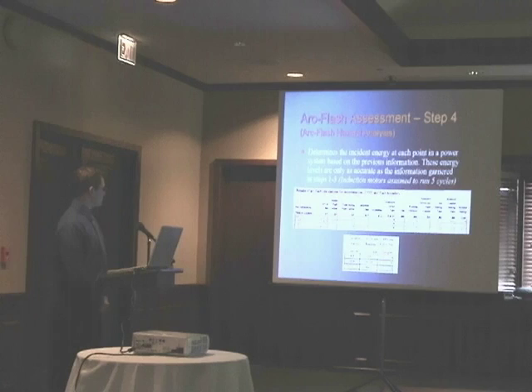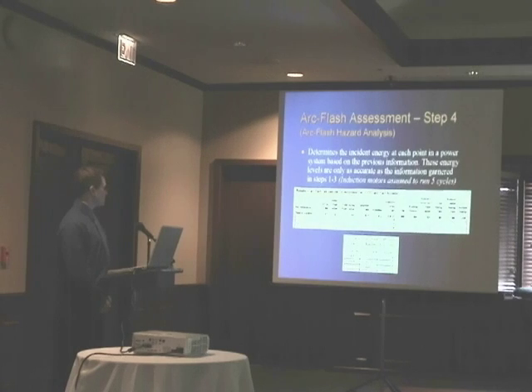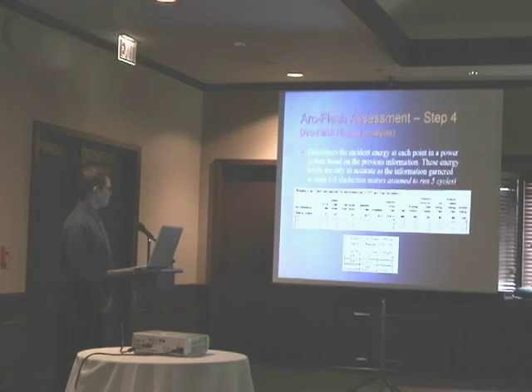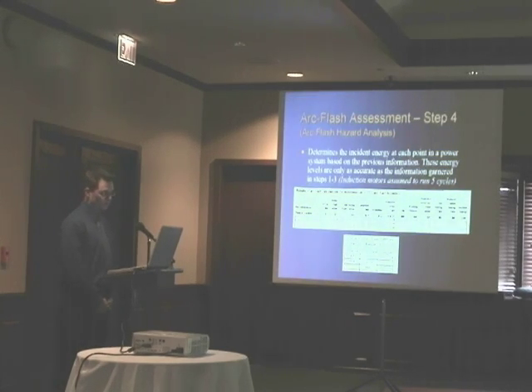I don't know if you can see this below here, but this just results in arc flash calculations from 23 kilovolts down to 4160 volts, and then 480 volts lastly. It's going to show you everything from your kilovolt bus all the way down to your incident energy. It's going to show you your working distances and your clearing times as well for your protective devices. In this particular study, the 4160 volt system or bus is the most dangerous, even though it's not the highest voltage. A lot of times this is the case with 4160 volts.